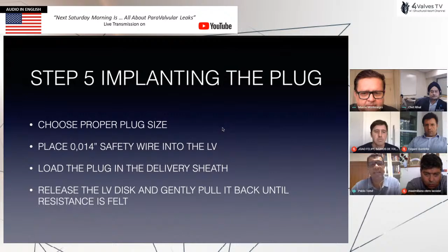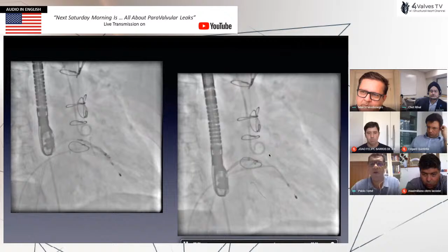We loaded the plug in the delivery sheath and released the LV disc, the first disc from the AVP2, and gently pulled until we felt resistance. As you can see in the right panel, right image, the disc is just touching the hole, and you can see the constraint here, as Dr. Chet told us, because it stretches and can conform to the anatomy of the leak.